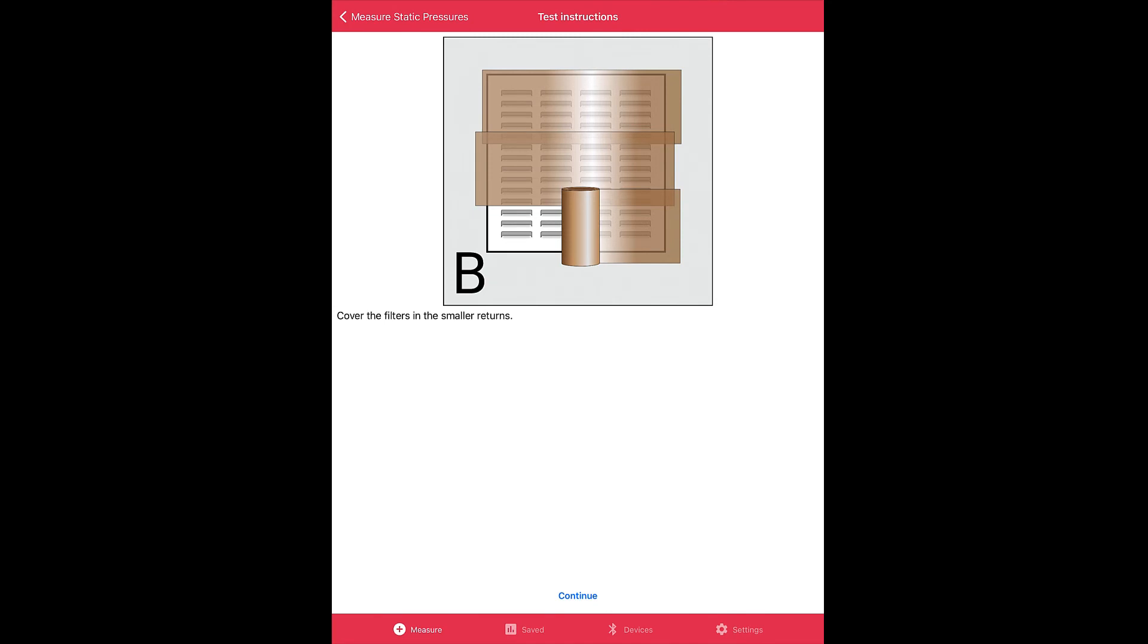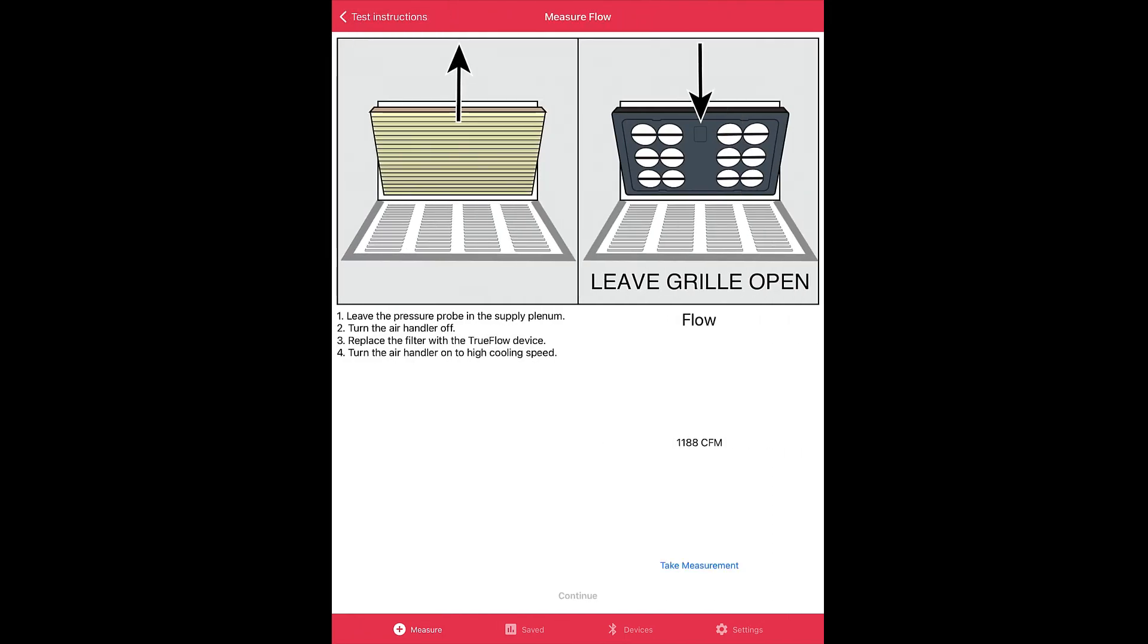Then it tells us to block off the airstream from the return of filter B by any means necessary. Click continue. Then filter surface area A, where the filter is, we will remove that filter and install the digital TrueFlow grid, and then we will take a measurement. That is how we will perform the double return workflow.